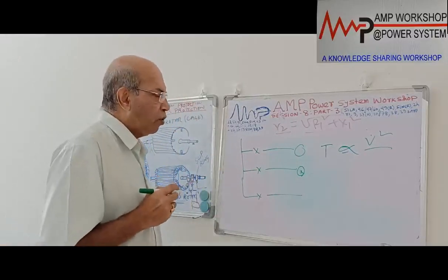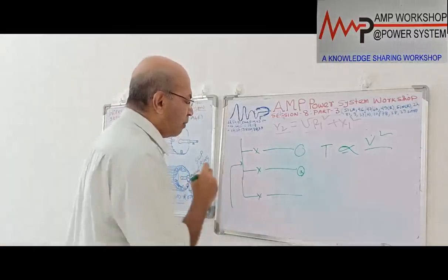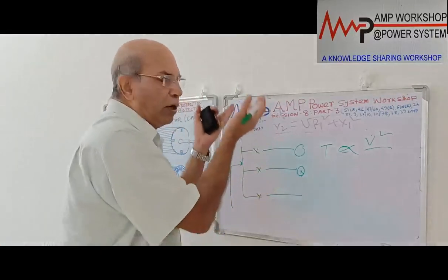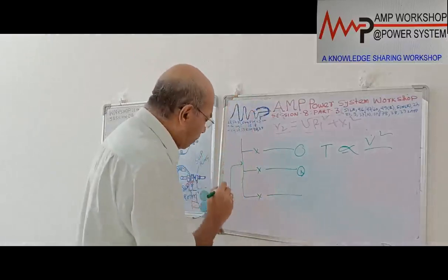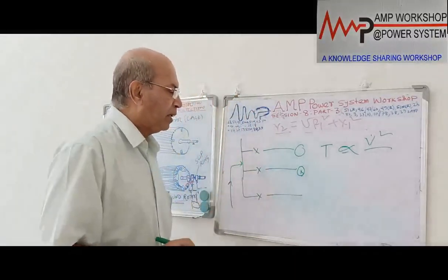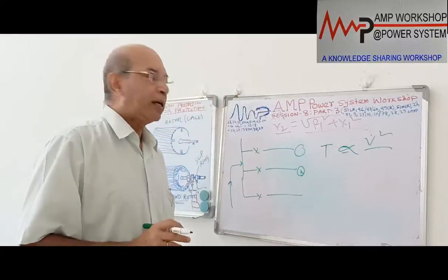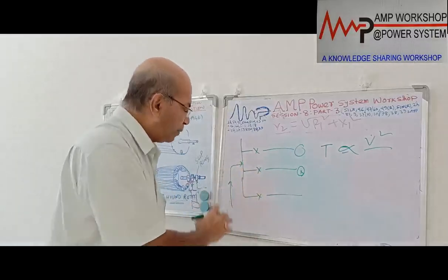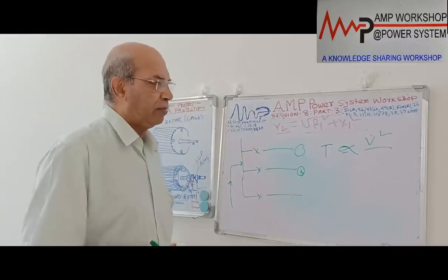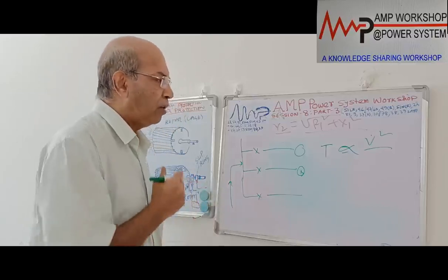If that is the case, what will happen after a certain time, if the power supply comes back? All the motors will start simultaneously, and the power system may not have enough capacity to cater for all the power. In that case, the power system upstream will trip. So there will be a total disturbance, and we cannot tolerate this. That is one of the things.